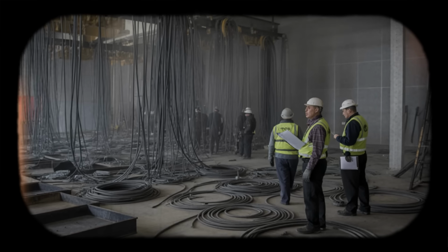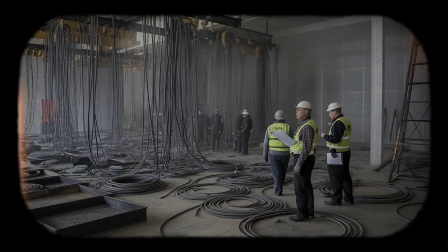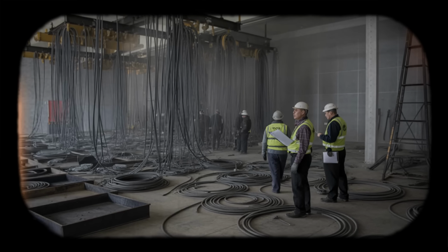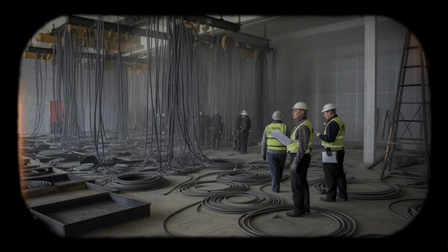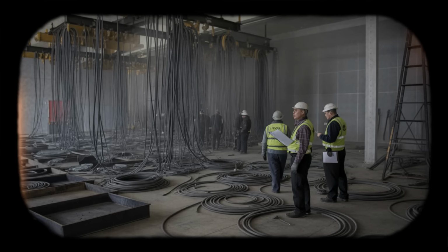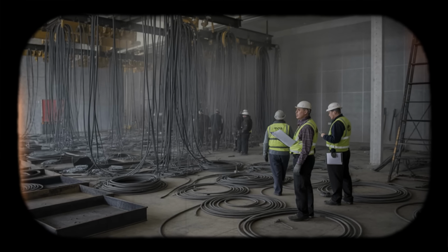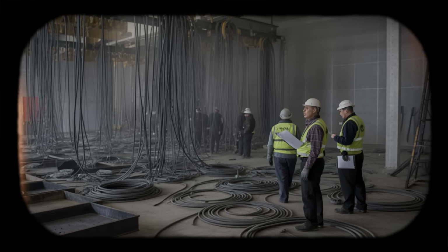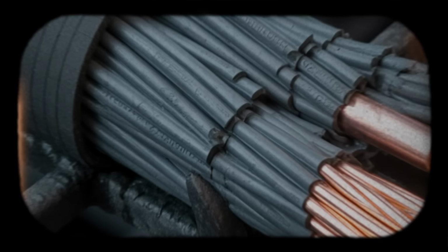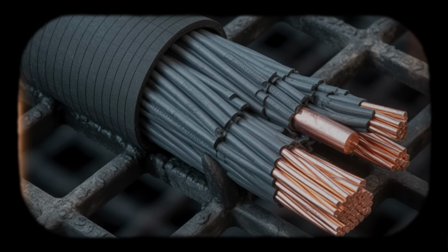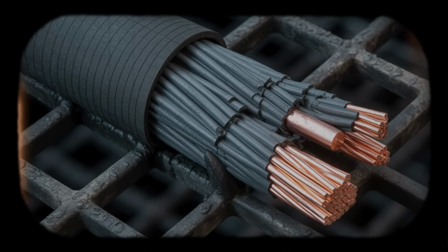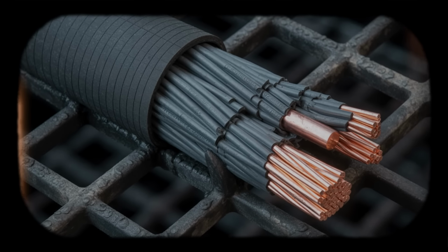The scale of the event becomes clear. 7 hours of active firefighting in a facility designed for complete fire suppression within minutes. Flames spread, threatened systems across 2 entire reactor units from a single ignition point. Over 1,600 cables damaged, 200 control circuits destroyed completely, requiring full replacement rather than repair.